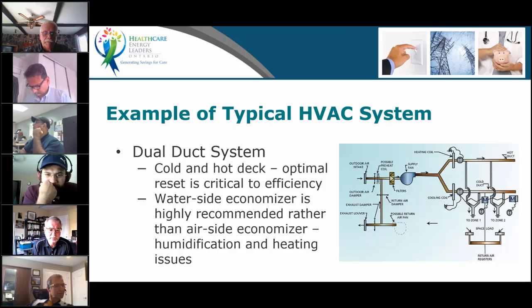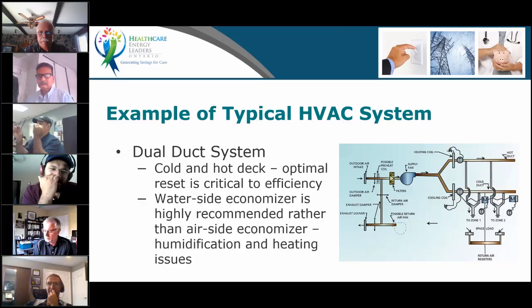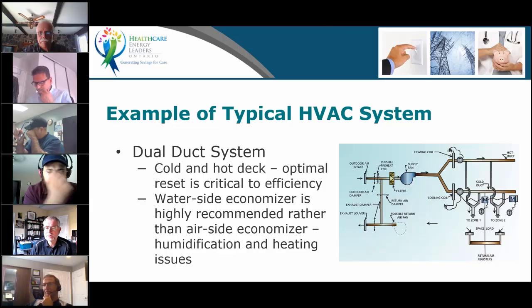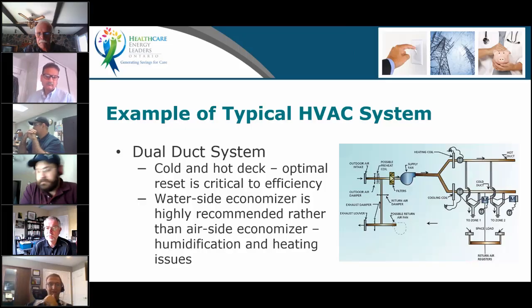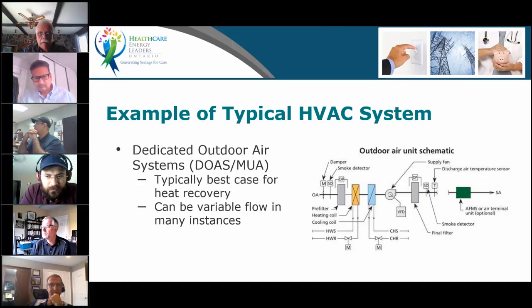Most of you are familiar with the standard. You know how those systems are defined. We call them, for example, a 2.6 or a 6.20. The first number is the number of fresh air changes you need. The second number is the total air changes in the space. So you need to have that in your CFR, make sure your system is providing what is needed, which becomes recommissioning basically, and then look at other measures such as, like I said, do I need heat recovery in this one? Can I install DCV in this one? So you need to know the type of system in order to judge if the measure is applicable.